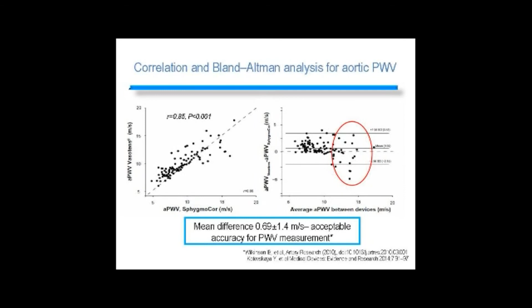According to the Artery Society gradation, the accuracy of pulse wave velocity measurement by the Vasotens technology was graded as acceptable. But you can see that Bland-Altman plots indicate that there was more discrepancy between pulse wave velocity values at high pulse wave velocity. Of course, it's an inherent limitation of one-side measurement of pulse wave velocity.